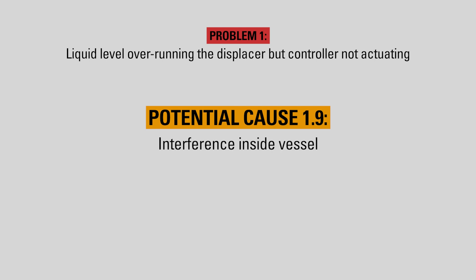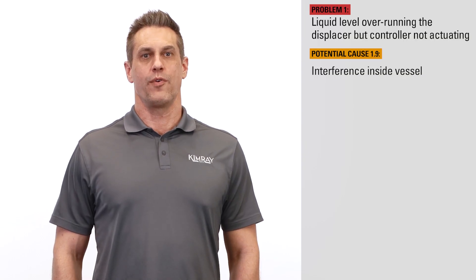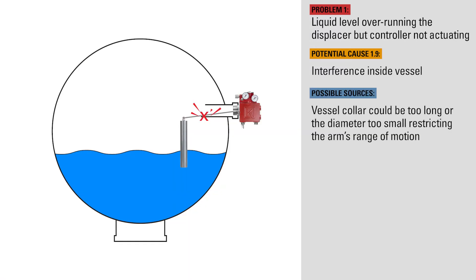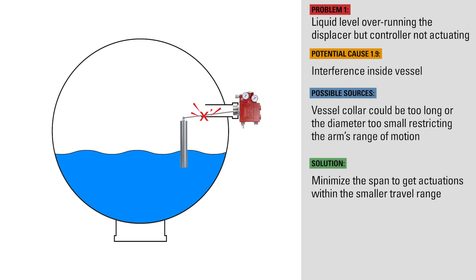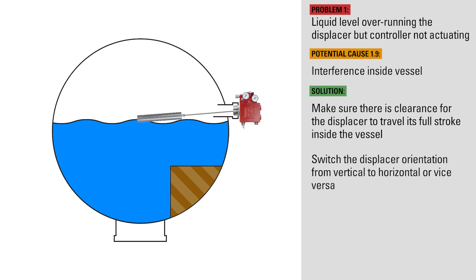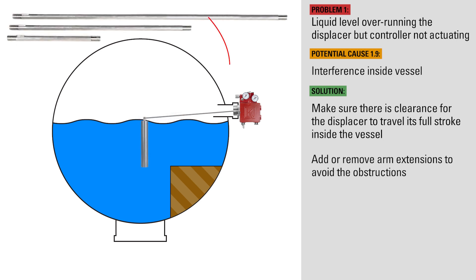If there's an obstruction inside the vessel not allowing full range of motion of the arm or displacer, this could prevent the controller from actuating. One possible restriction could be the collar inside the vessel being too long or the diameter too small. If this is the case, you can try minimizing the span to get actuations within the smaller travel range. Make sure there's clearance for the displacer to travel its full stroke inside the vessel. If there isn't, you can try switching the displacer orientation from vertical to horizontal or vice versa, or adding or removing arm extensions to avoid the obstructions.